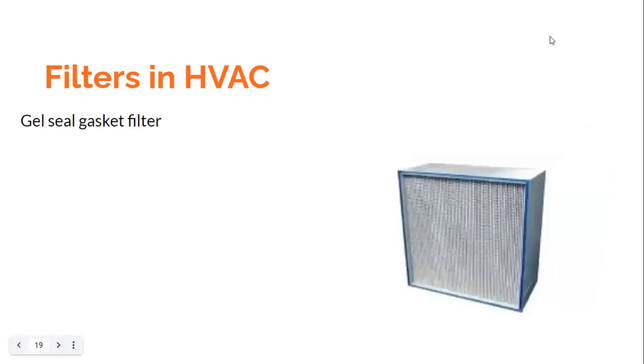One more filter to discuss is the gel seal gasket filter. This filter type uses a special type of gasket made of a gel-like material — either silicone or polyurethane. This gel becomes semi-solid once set. The gel is provided either in a channel in the filter or in the mounting frame, and a knife edge fixed in the mating component pierces through the gel, providing a leak-free seal. This self-healing gel gives a foolproof leak-free sealing, making it suitable for high efficiency HEPA filter applications.